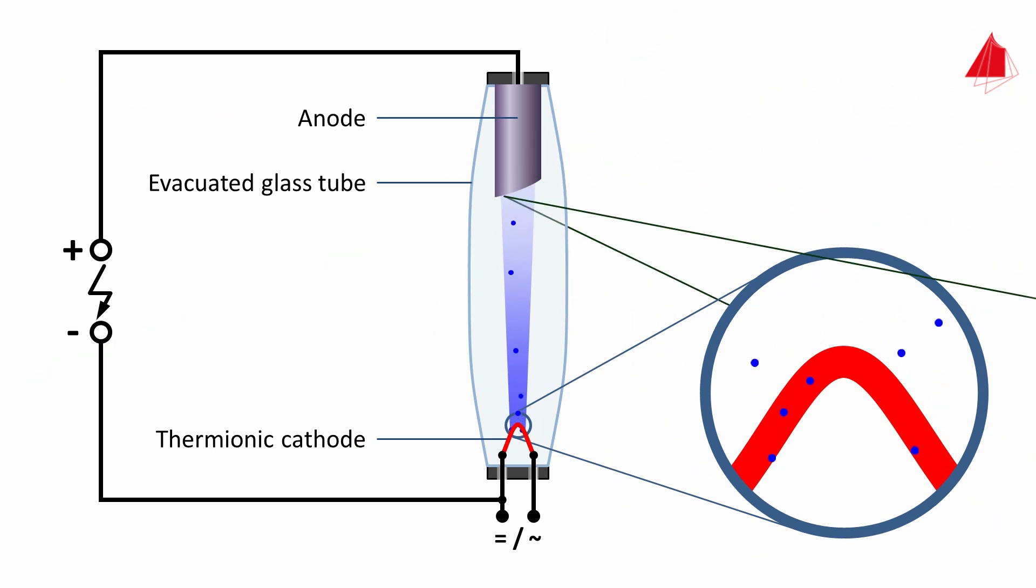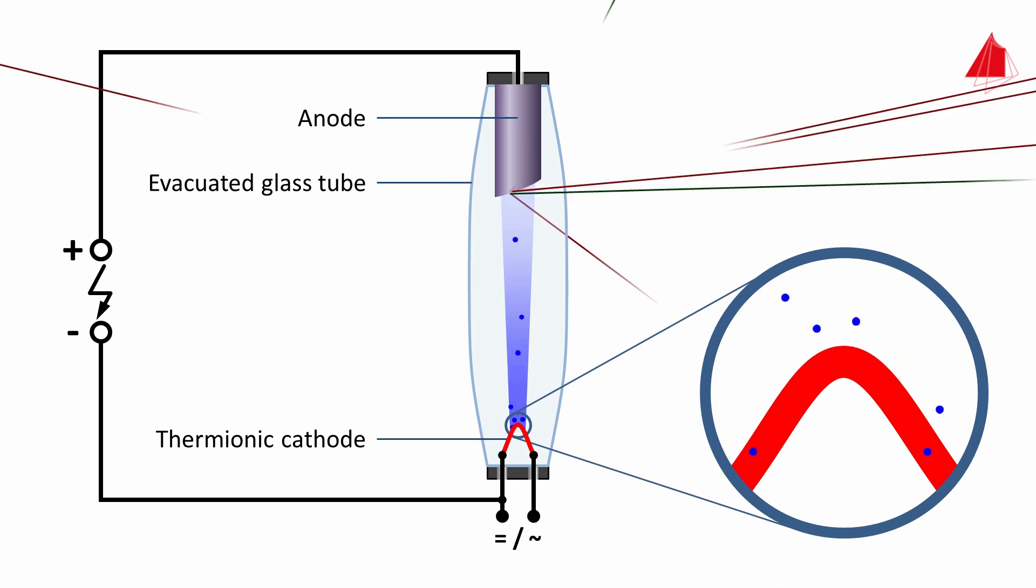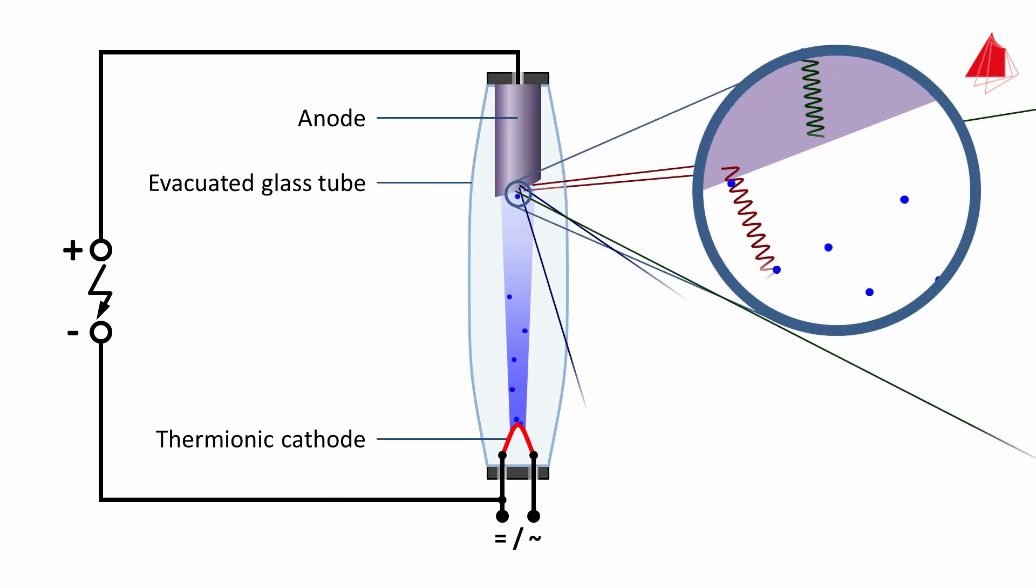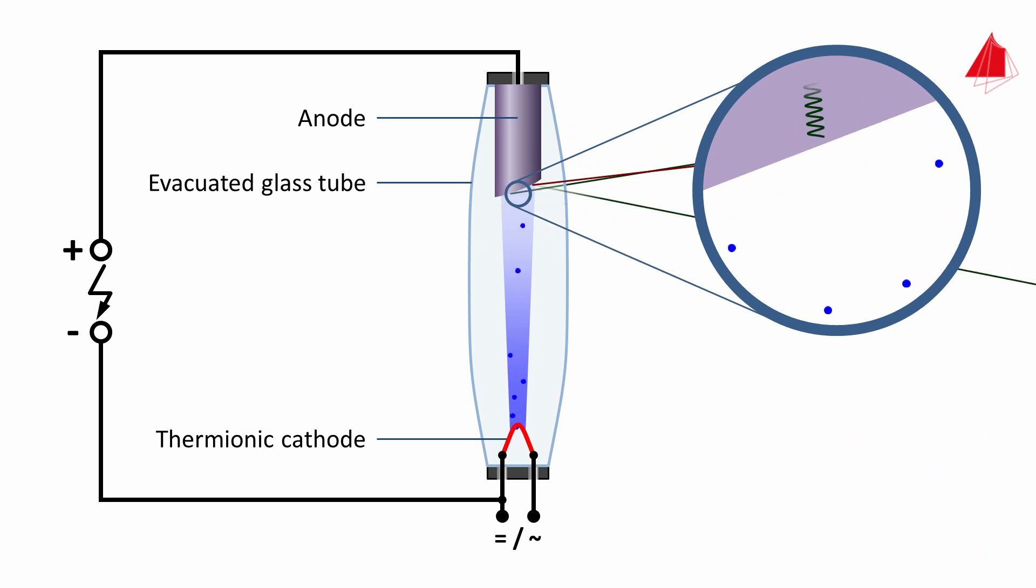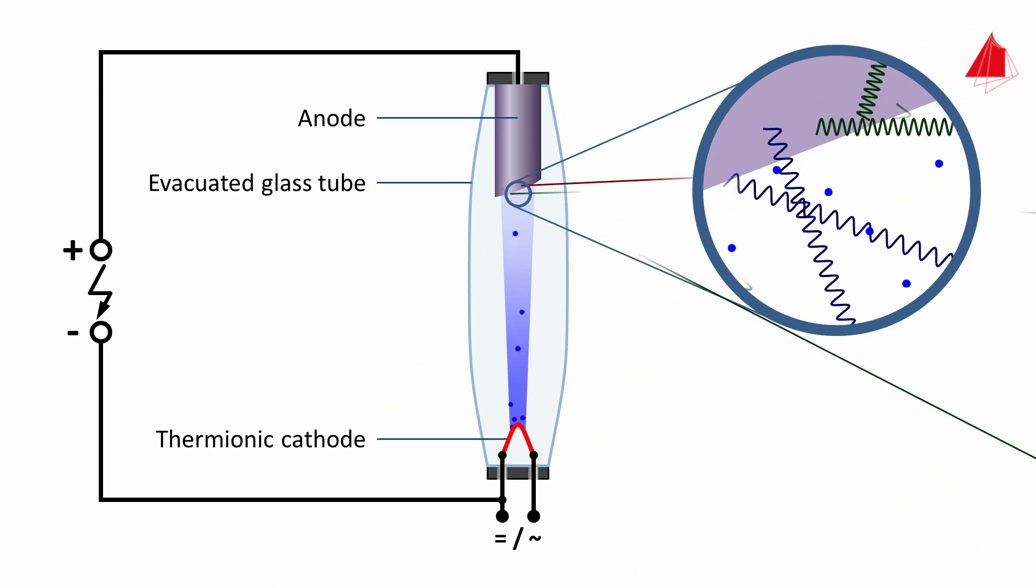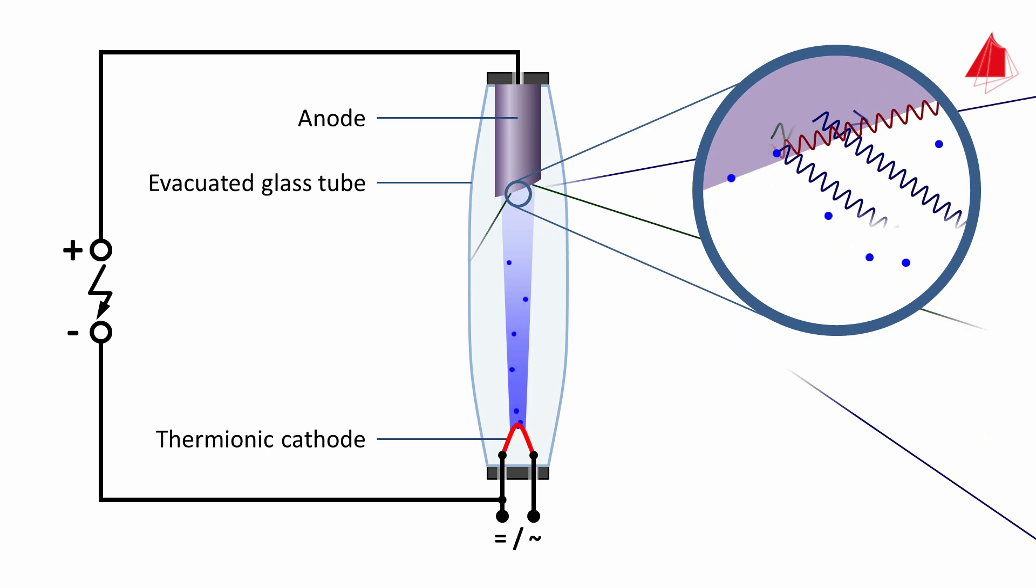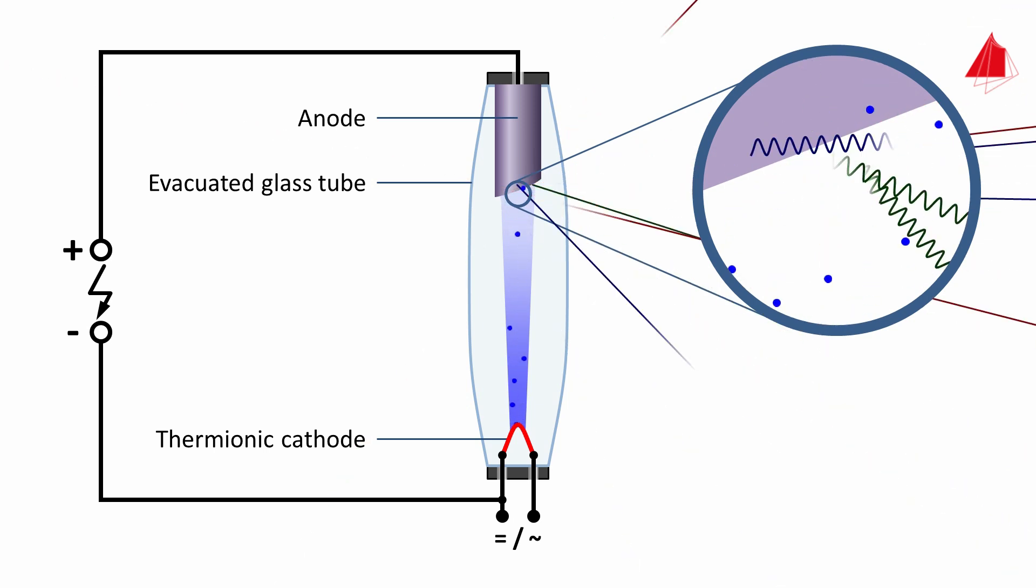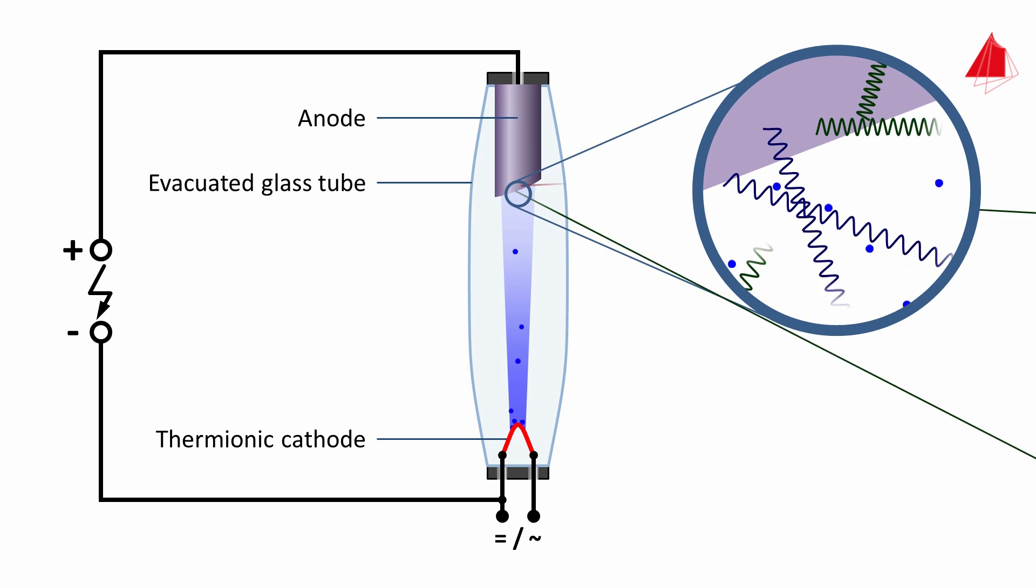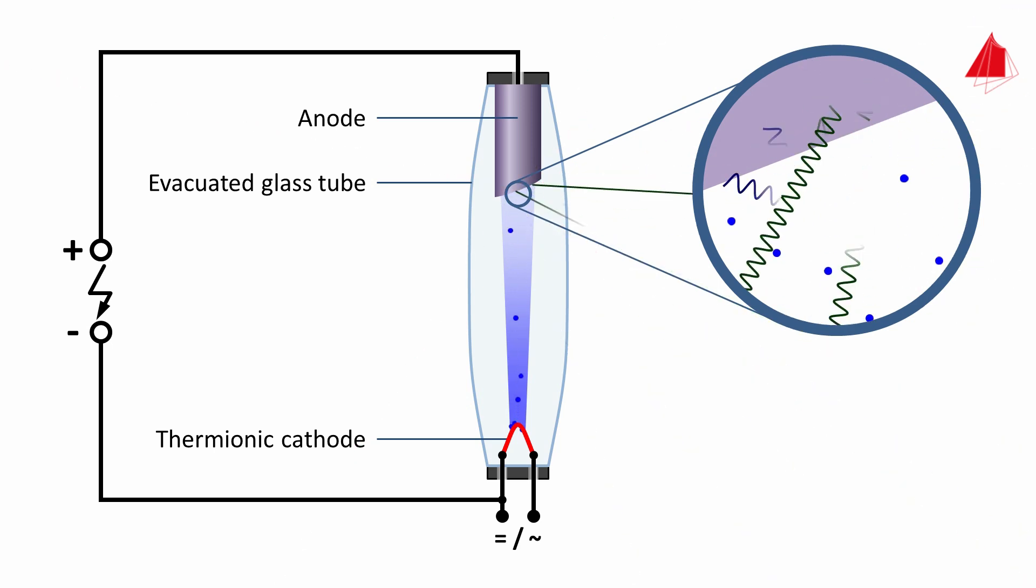An electron beam is formed. The electron beam collides with the anode at high velocity. The anode material slows down the electrons within a very short distance. This generates the desired x-radiation, but unfortunately also a lot of heat which has to be dissipated by cooling.